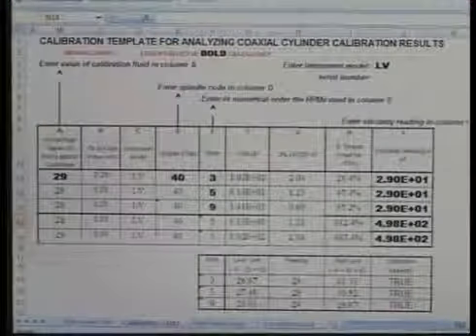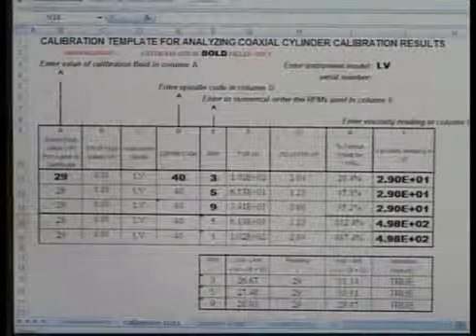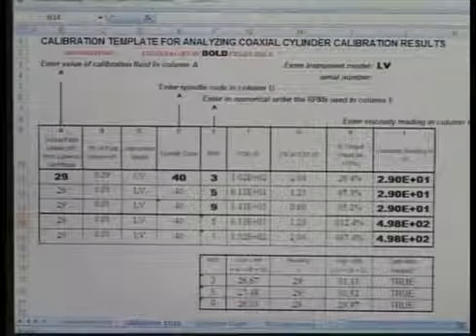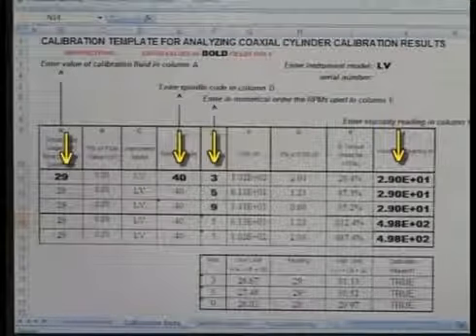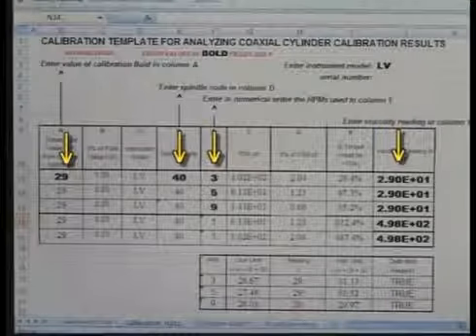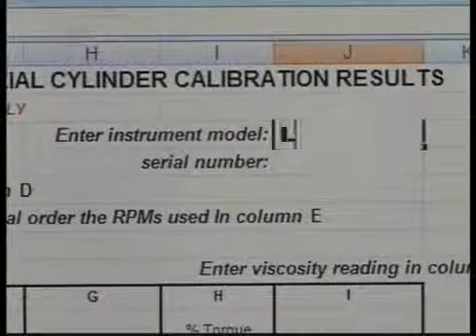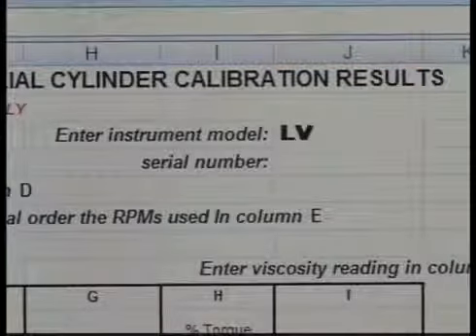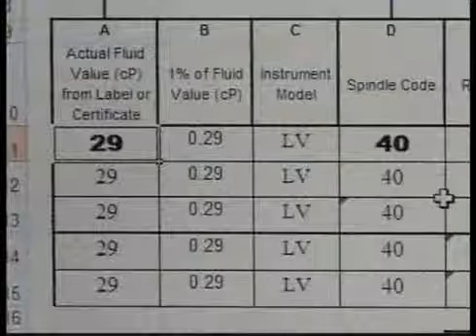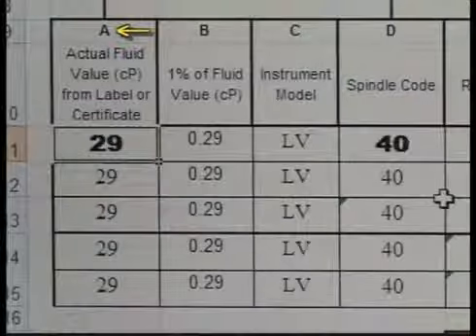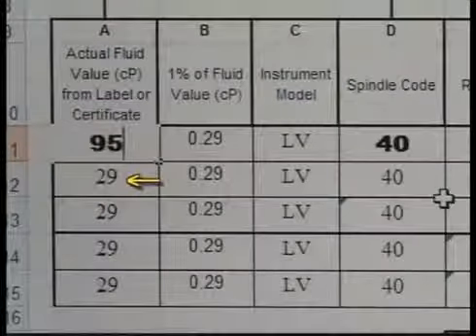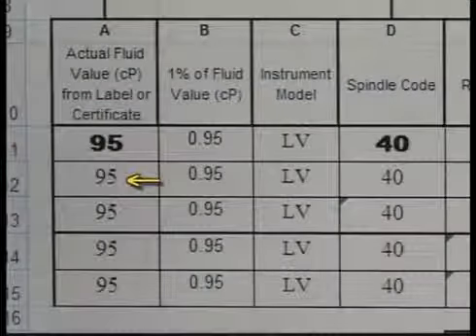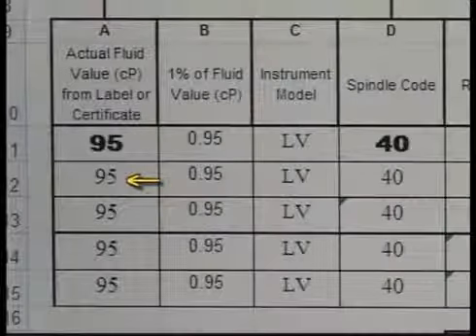To see what these tolerances mean, let's look at this calibration worksheet. Enter data in the bold fields. You will need to overwrite the existing data. First, enter the spring torque of your instrument. In this case, this will be an LV. Enter the actual value of the fluid in column A. The remaining fields in this column will automatically update as this value will not change.